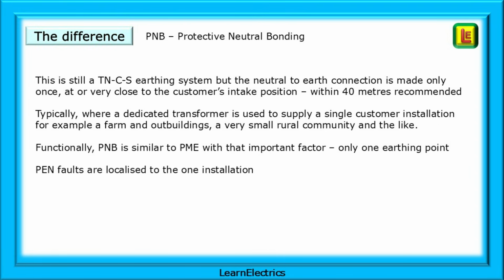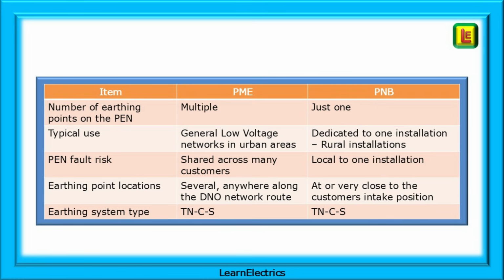PNB, or protective neutral bonding, is still a TNCS earthing system, but the neutral to earth connection is made only once, at or very close to the customer's intake position. Within 40 metres is recommended. Typically installed where a dedicated transformer is to be used to supply a single customer installation, for example a farm and outbuildings, or a very small rural community, and the like. Functionally, PNB is similar to PME, with that important factor, only one earthing point, and the PEN faults are localised to that one installation. This short table compares some of the differences between the two systems.